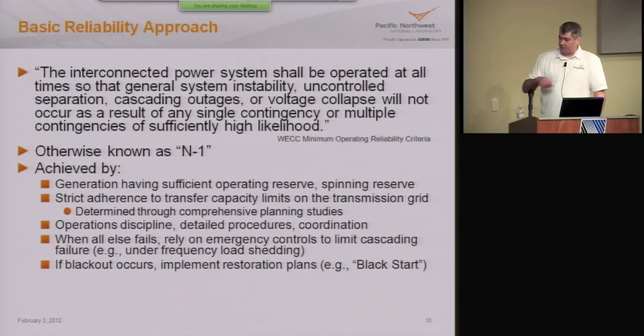Just a quick note about this black start process. One of the reasons this is so difficult is a big power plant requires off-site power in order to operate. You can't just walk up to a coal plant and hit the on button and have it start generating power. It needs off-site power to get the pumps going, the fans going - there's a lot of power required before it generates its first watt of electricity. So a black start plan involves having certain units that are black-start capable.